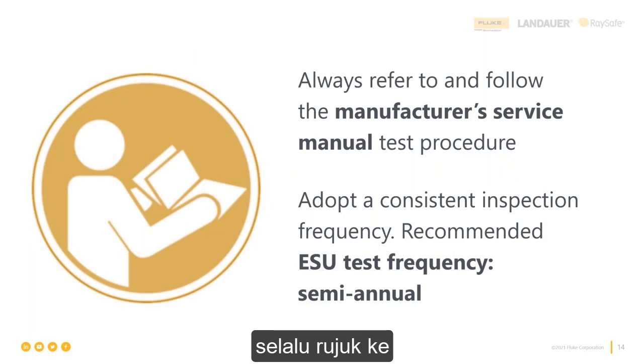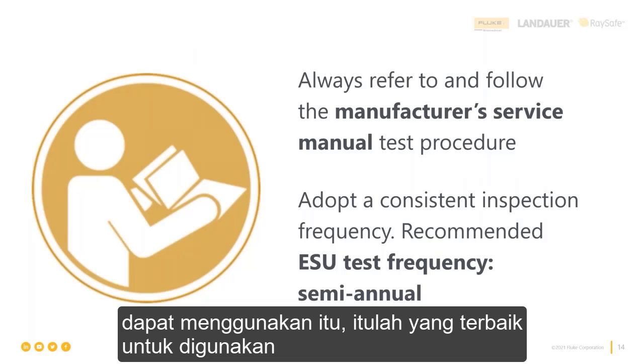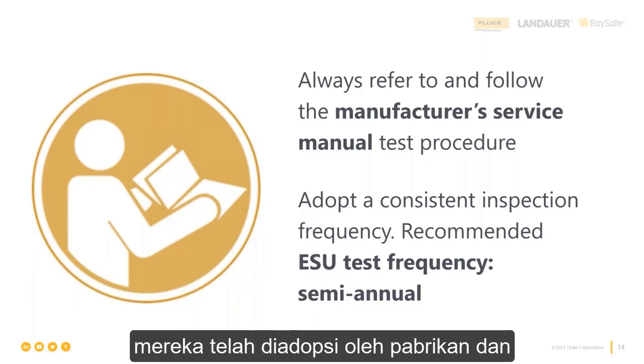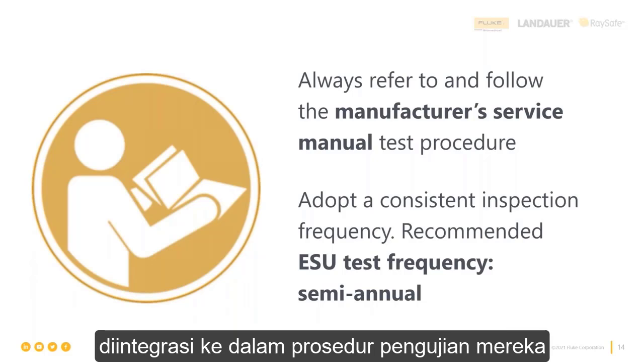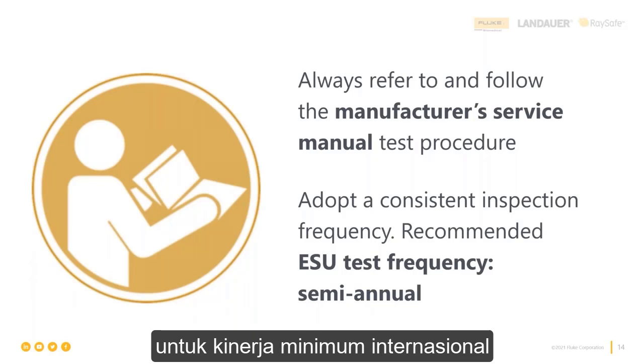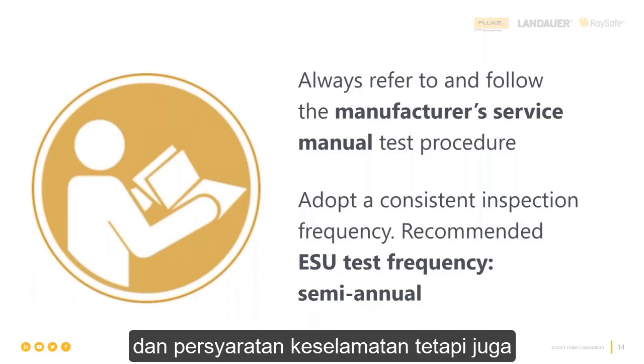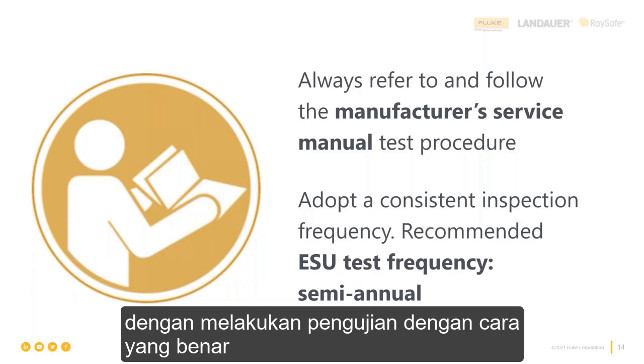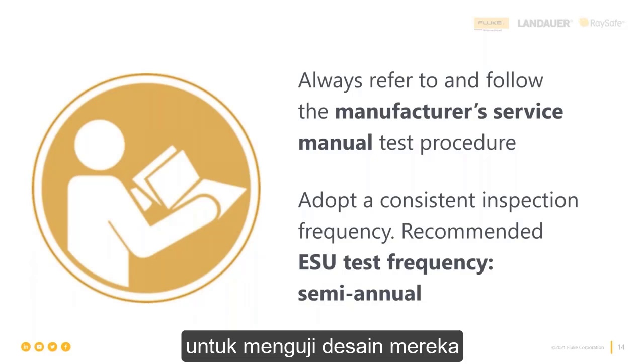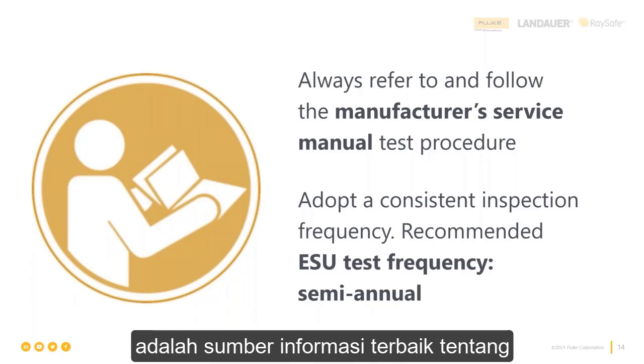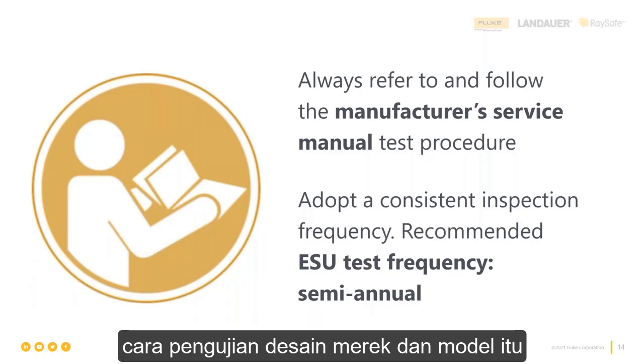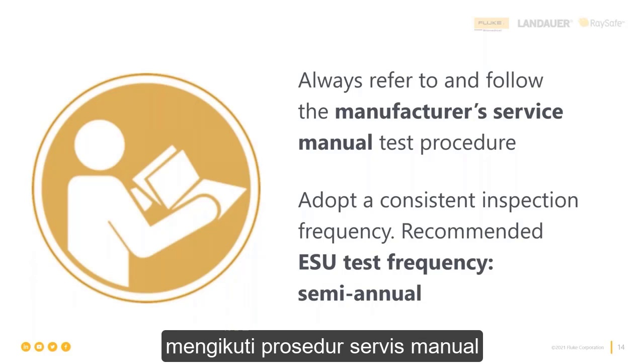Always refer to the manufacturer's service manual test procedure, and whenever you can use that, that's the best one to use. The reason is because the manufacturer has adopted and integrated into their test procedure not only the tests that are important for international minimum performance and safety requirements, but also doing the testing in a way that properly tests their design, because the manufacturer of the ESU is the best source of information about testing that brand and model design. So you want to make sure you're following the service manual procedure.